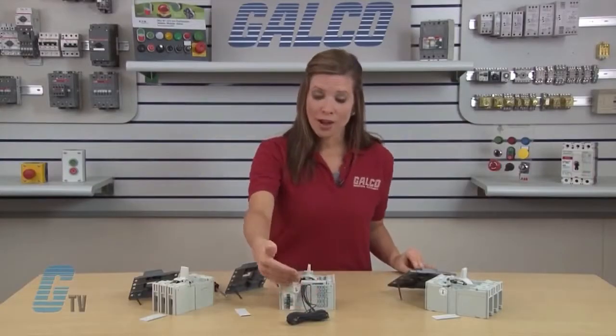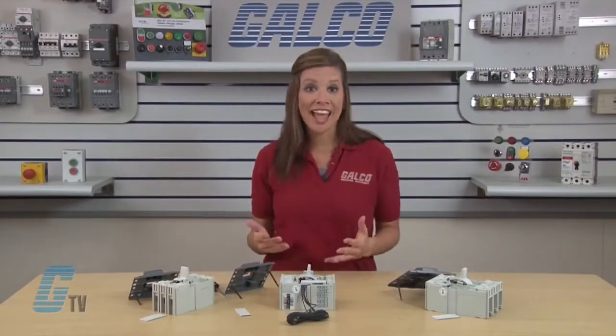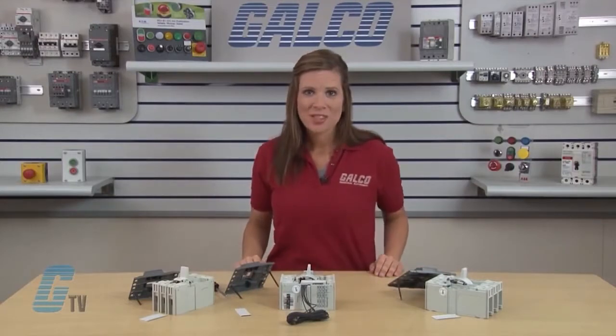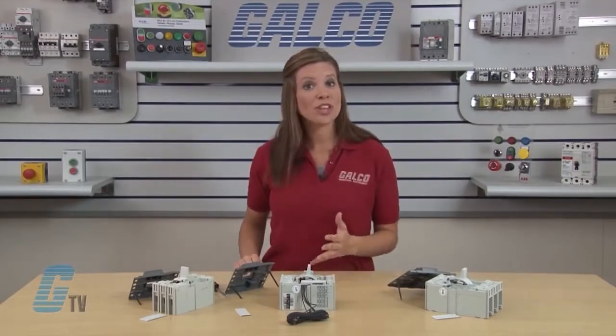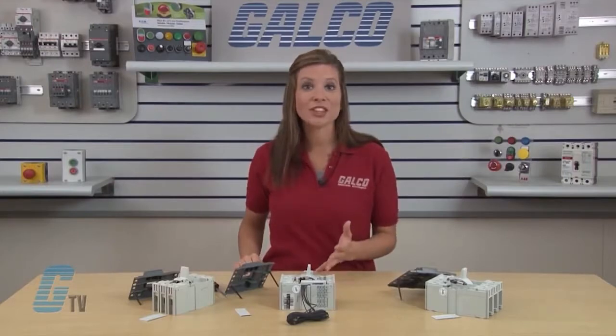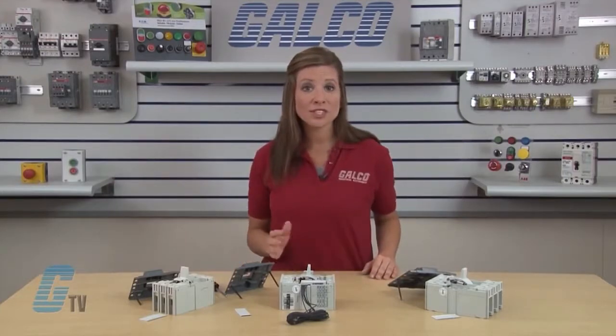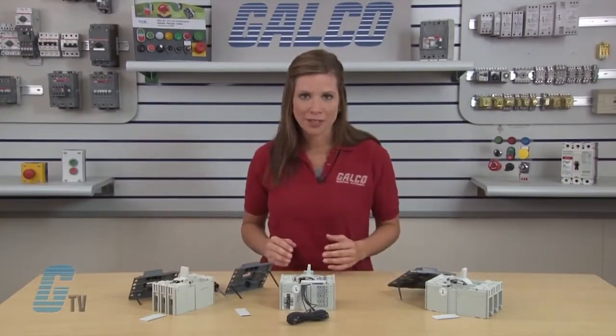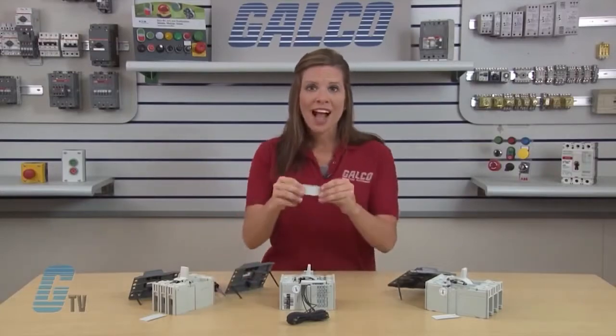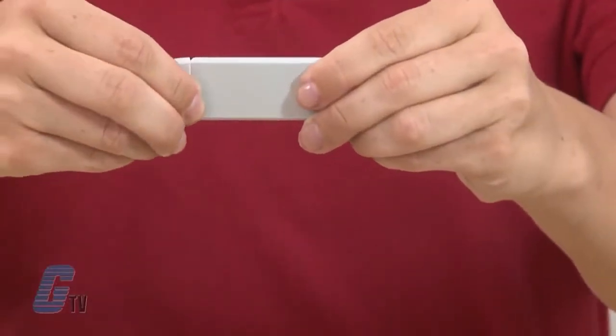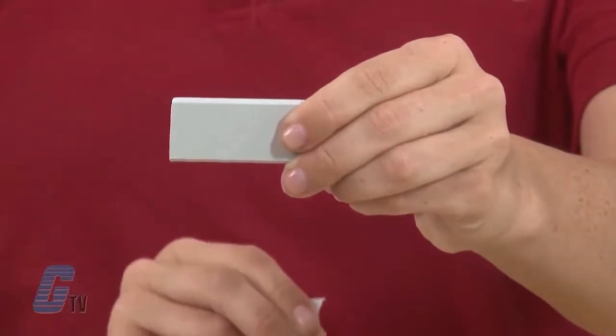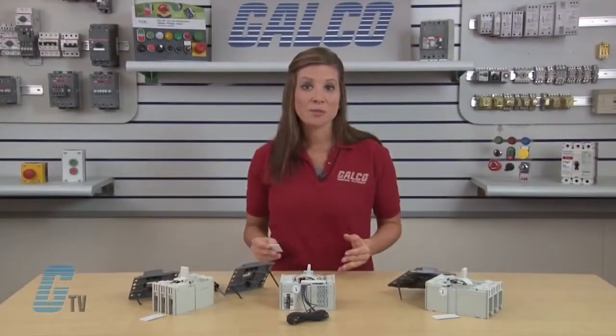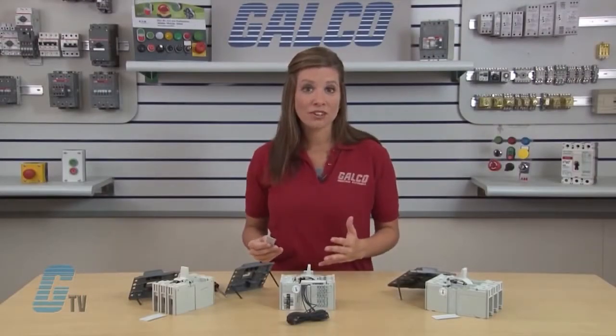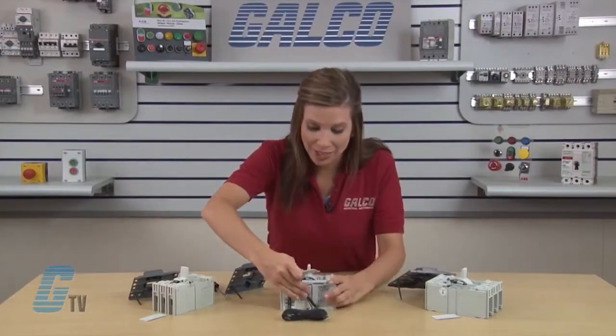The wires should be routed along the wire channel on the outside of the circuit frame. The wire channel cover can be shortened so that the wires can exit the channel right at the surface of the enclosure panel when the circuit breaker is surface mounted. To shorten the cover, I'll bend it back and forth here where it has been pre-scored and notched by the manufacturer until the part separates. Then the wire channel cover can be slid back into place.